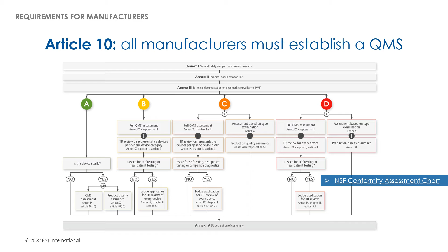Obviously, there is much to consider when declaring conformity or when applying for a conformity assessment at your notified body. To get a better handle, and instead of flipping pages all the time, I added a link to the NSF conformity assessment chart. You can use this printable chart to refer to the relevant parts of the IVDR that contain requirements based on each risk class that you need to observe for the conformity assessment of your product.